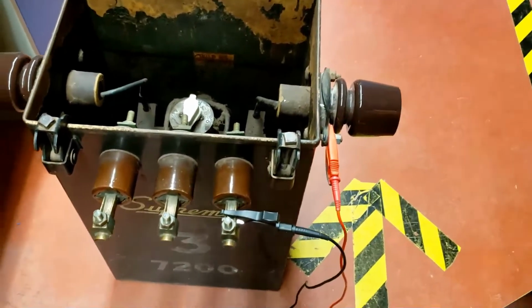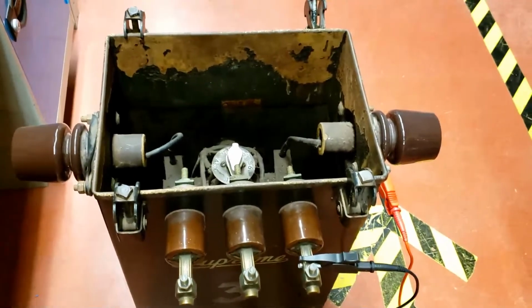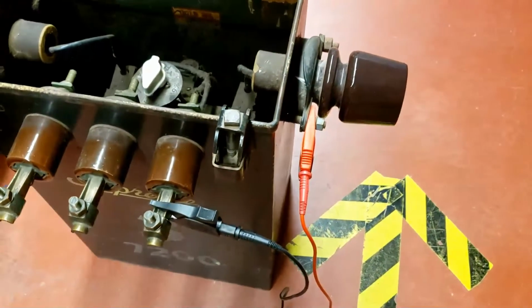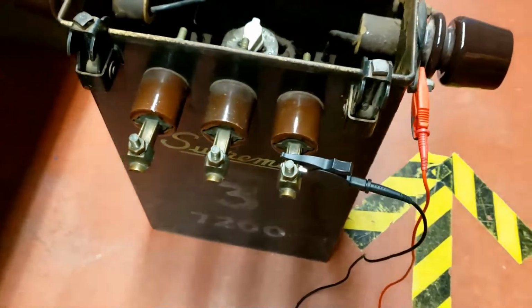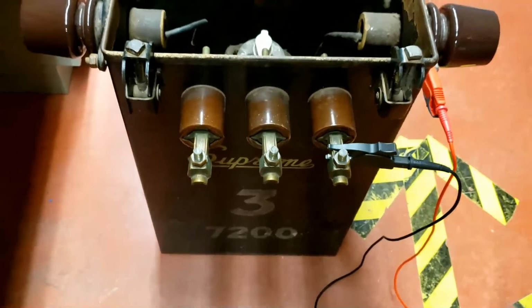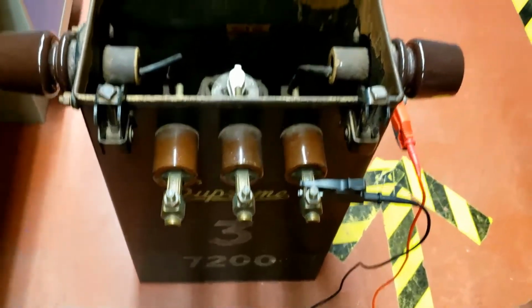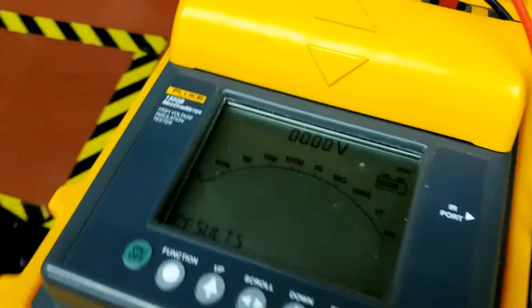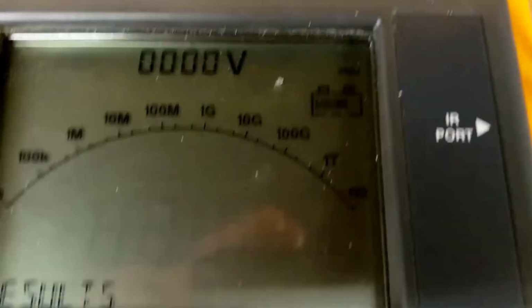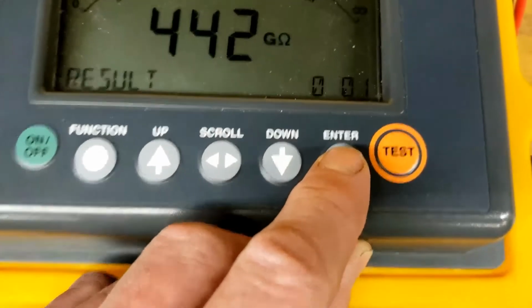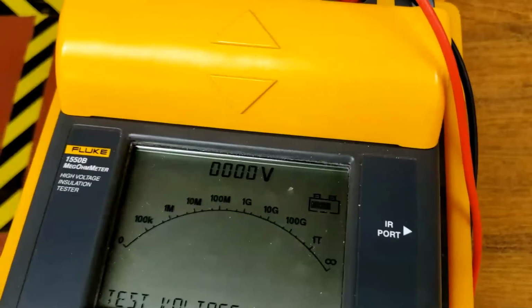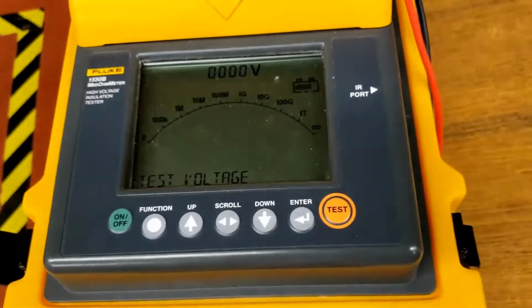So I've put my leads across this poletop transformer. I'm hooking one onto a ground, and I'm just hooking onto one of the low voltage outputs. So these are 240 volts. And typically test at double the voltage. So that's set to 250. I'm going to set that to 500. All right, now we're ready to test.